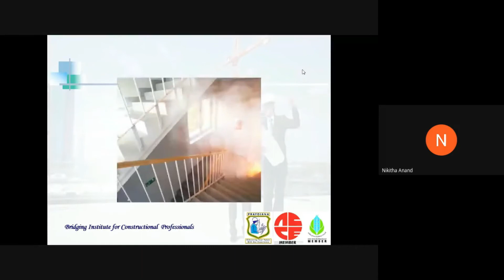See, this is one photo of a staircase fire. And see, how to give this permanent ventilation: there will be some cross-sectional area for the enclosure. In that, 5% of the top level will be given only for ventilation. This is how the calculation should be done according to NBC. And the roof of the shaft shall be at least 1 meter above the surrounding roof, and there will be no glazing or glass bricks in any internal wall of the staircase.